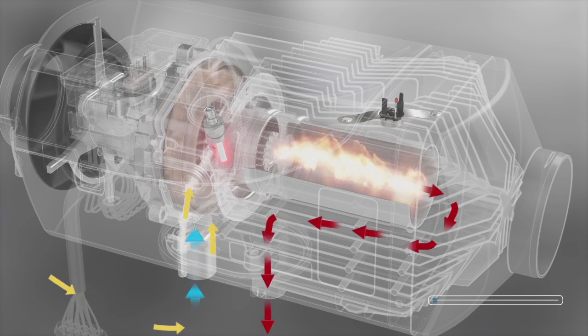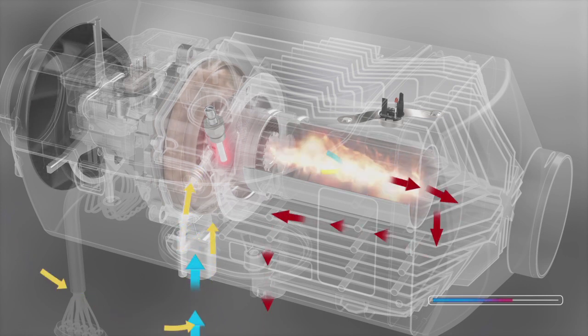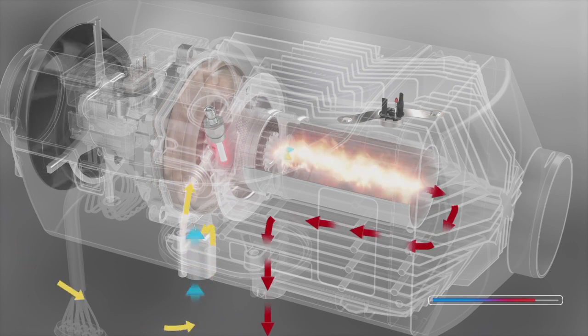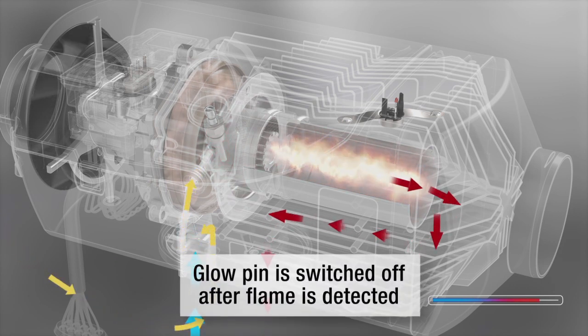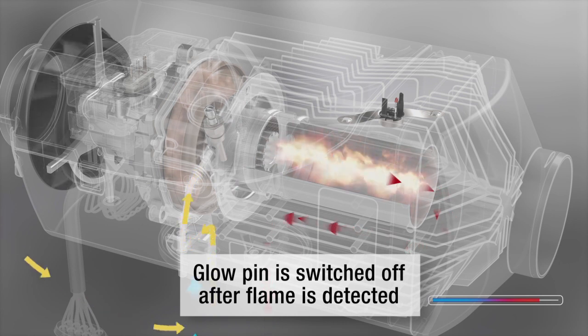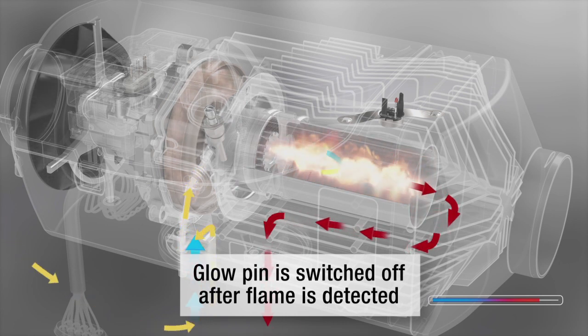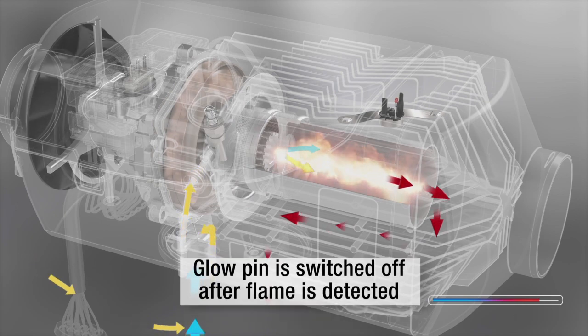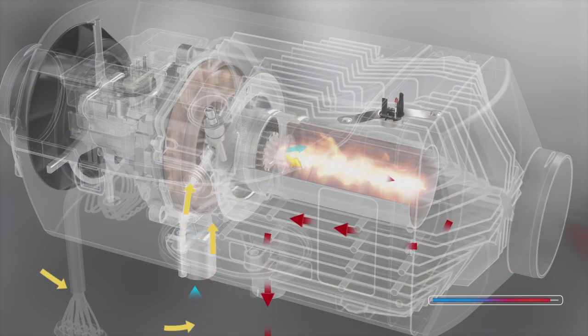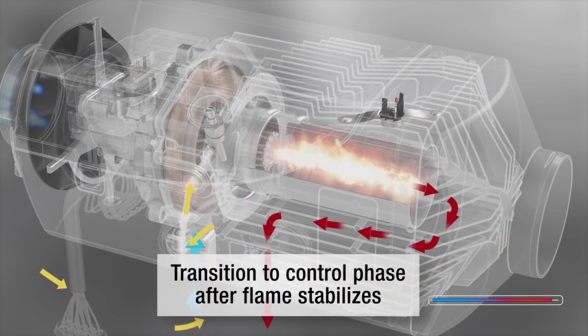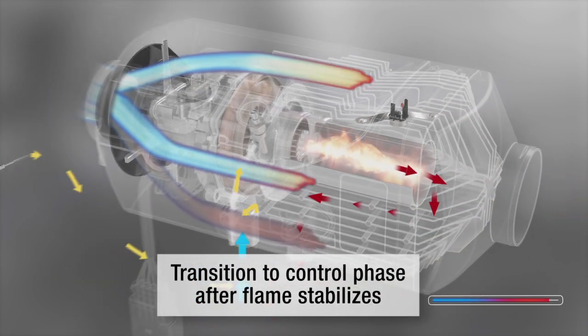The combination sensor registers the temperature on the heat exchanger. If a programmed rise in temperature is reached within a certain time, a flame is detected and the glow pin is switched off. Combustion is then powered up to the maximum level. Once the flame has stabilized, the heater switches to the control phase.